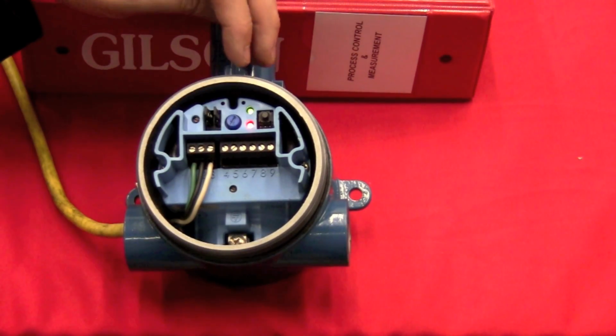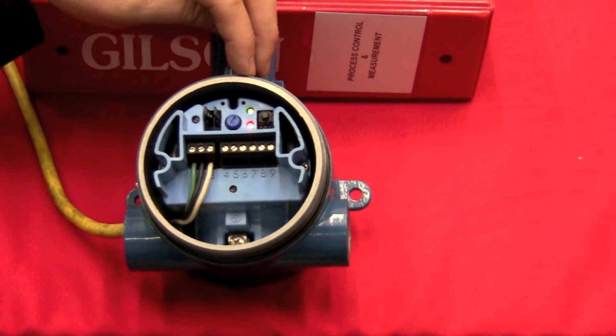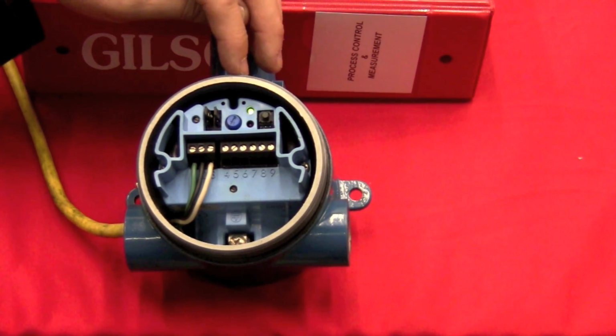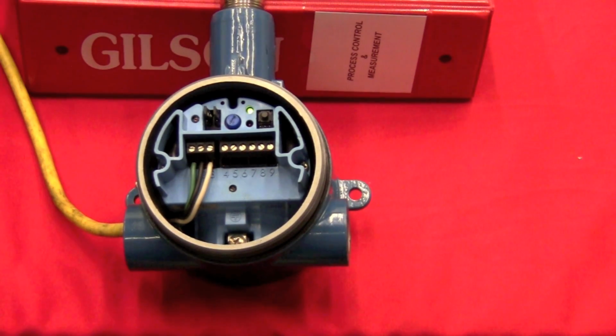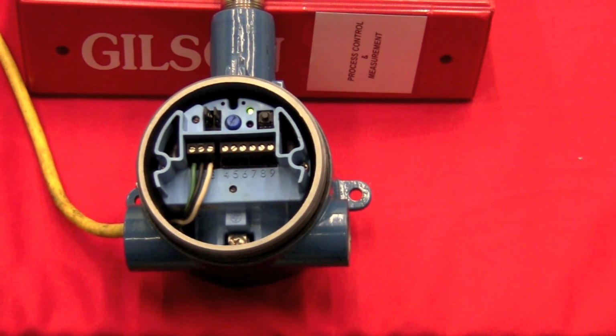As you can see, it's still flashing here, and in a few seconds it should stop, and then the green LED light will remain lit, indicating we have power to the unit, and the red LED will go out, indicating that we're not in alarm. As you can see, it came out of calibration. Now, if I touch the probe, I will put it in alarm, and then it will come back out of alarm when I release it. And that is a complete full setup of the Drexelbrook point level switch.